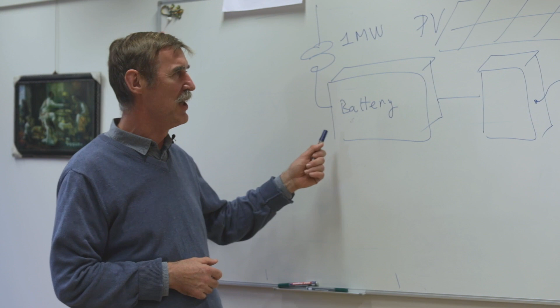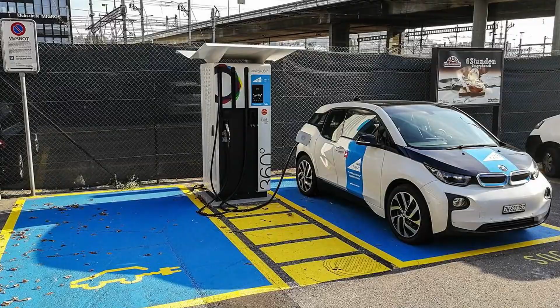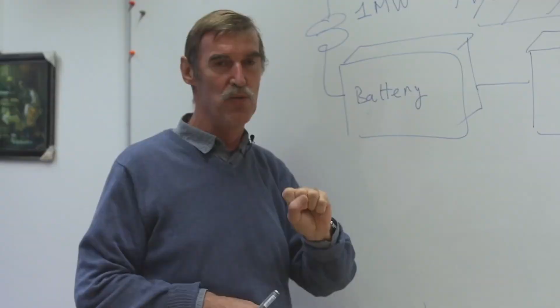What the Comelec system does is use the results of monitoring with PMU infrastructure of the state of the grid and react to this state by modulating the power consumed by electric vehicles and also the power generated by the solar panels, in order to provide things like primary frequency support to the main grid, or additional capacity to a charging station. With the PMU infrastructure, we can monitor exactly what the building is doing.